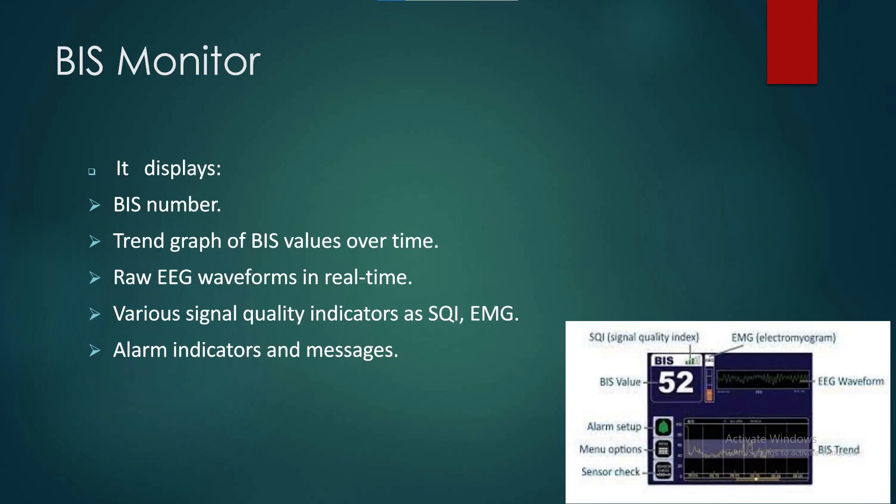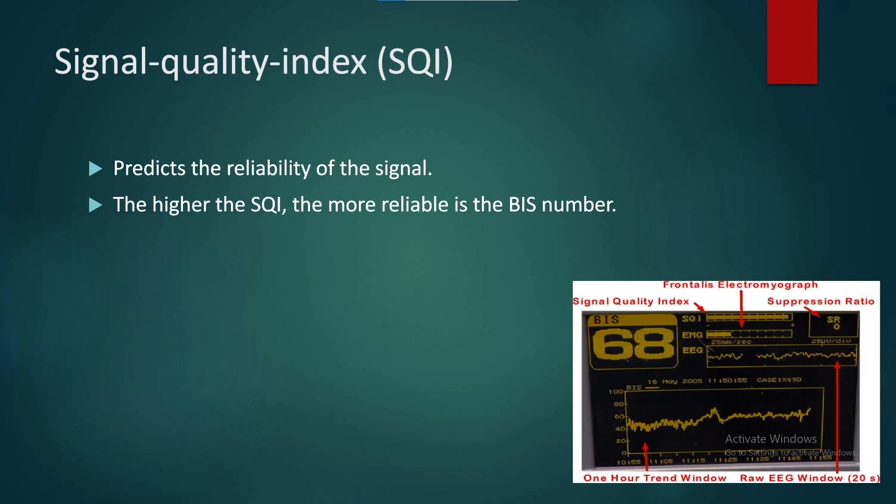The BIS Monitor displays the BIS number, a trend graph of BIS values over time, raw EEG waveforms in real time, and various signal quality indicators such as SQI, EMG, alarm indicators, and messages. The Signal Quality Index, or SQI, predicts the reliability of the signal — the higher the SQI, the more reliable the BIS number.